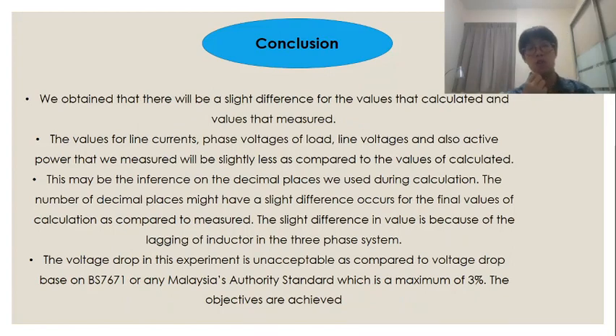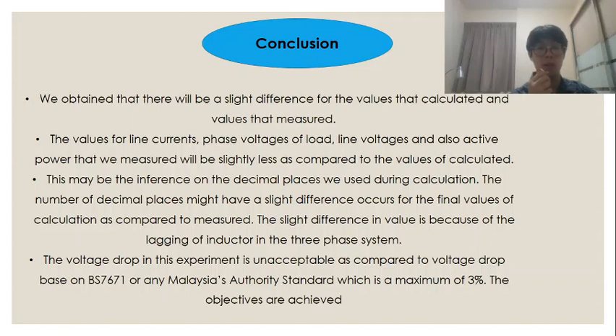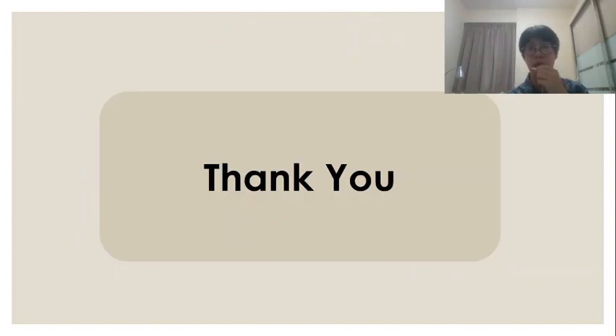For the conclusion: there will be a slight difference between the calculated and measured values. The values for line currents, phase voltages of load, line voltages, and active power measured are all slightly less than the calculated values. This may be due to rounding of decimal places used during calculation, and the slight difference is also attributed to the lagging of inductors in the three-phase system. The voltage drop in this experiment is unacceptable as compared to the standard based on BS7671 or any Malaysia authority standard, which permits a maximum of 3%. Lastly, the objectives are achieved in this project. Thank you for listening to my project sharing.